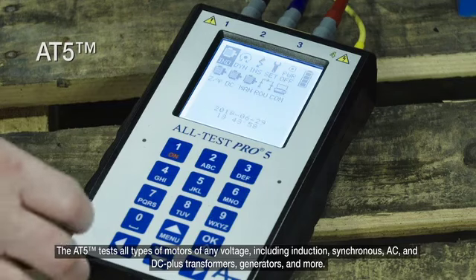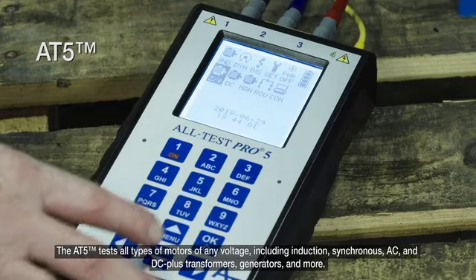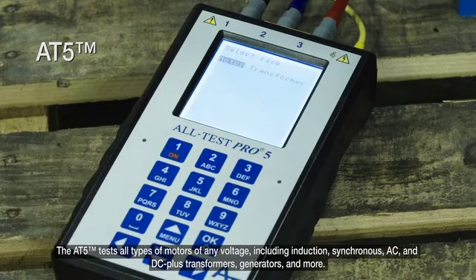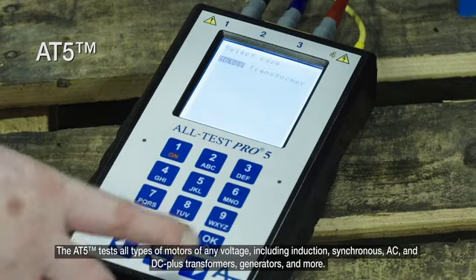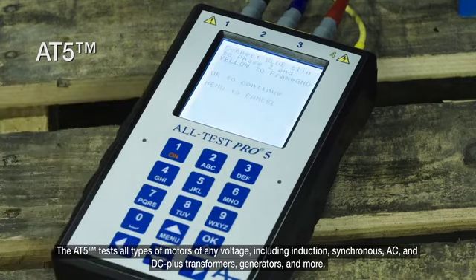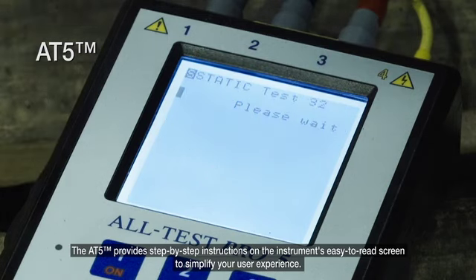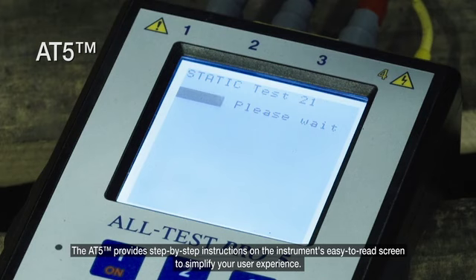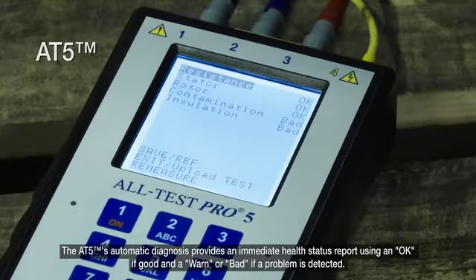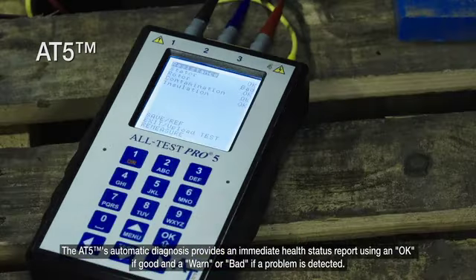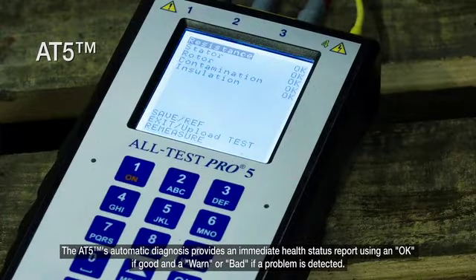The AT5 tests all types of motors of any voltage, including induction, synchronous, AC, and DC, plus transformers, generators, and more. The AT5 provides step-by-step instructions on the instrument's easy-to-read screen to simplify your user experience. The AT5's automatic diagnosis provides an immediate health status report using an OK if good and a warn or bad if a problem is detected.